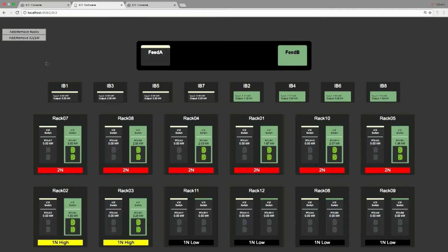So let's fail Feed A. Within 10 milliseconds, you can see all of the racks in red are maintaining availability. The B side has doubled in power capacity and is maintaining that rack. And the least critical racks in black have been throttled back by just the amount of the deficit.